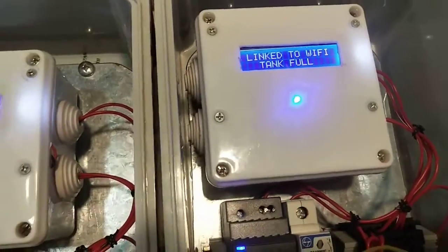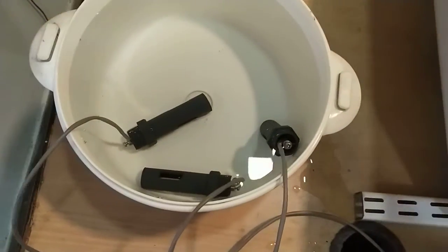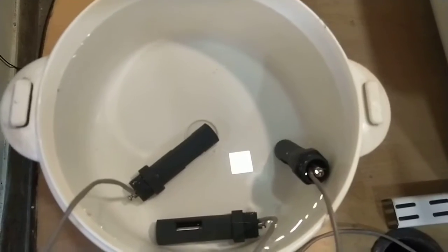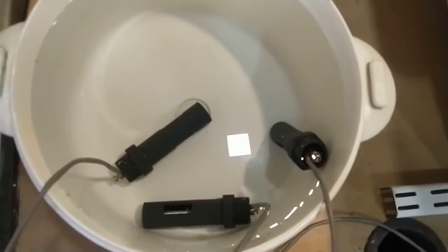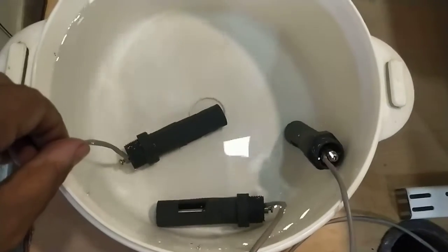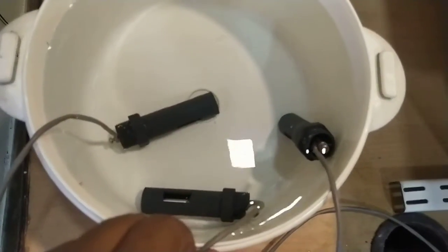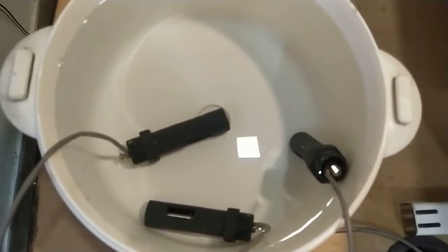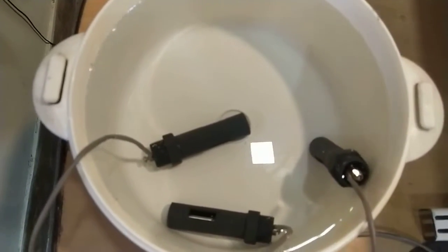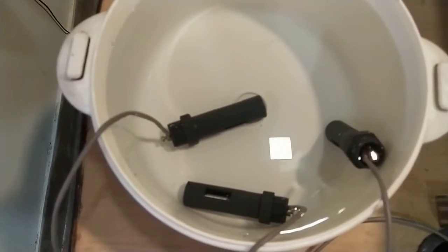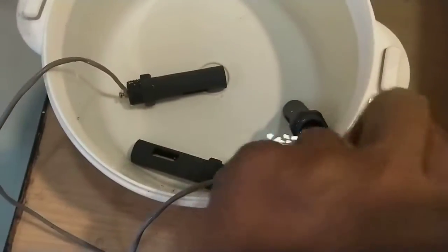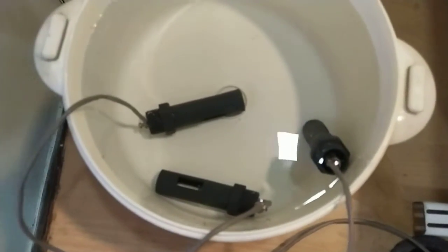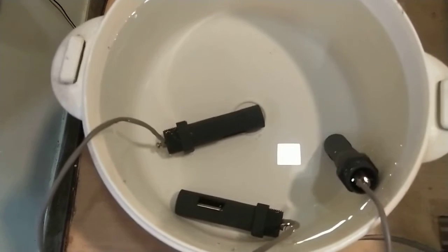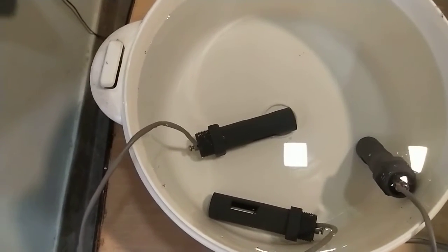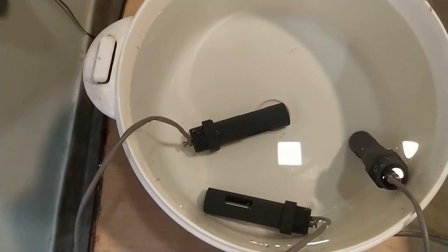You see here what is happening is, I'll show you the brief experimental setup that I have made in my office. Here are the three probes. The probe on the left is the reference probe. This probe is the middle probe or the low probe, when the water drops below the low probe, the pumps should start. And this last probe is the high probe, up to which the tank level is allowed to go up, beyond which the pump controllers would trip the pump.